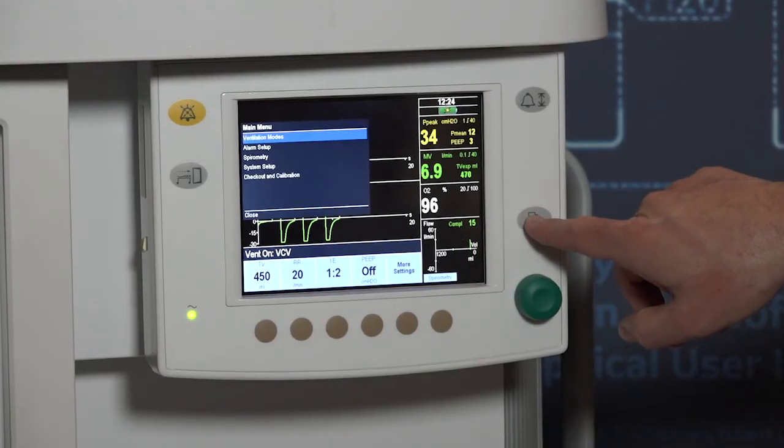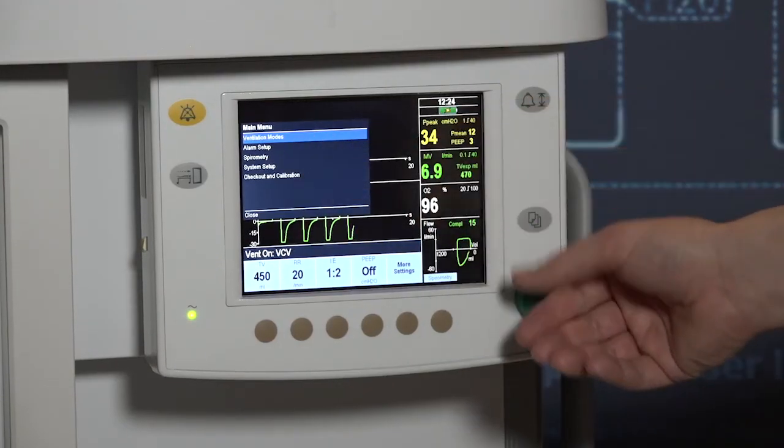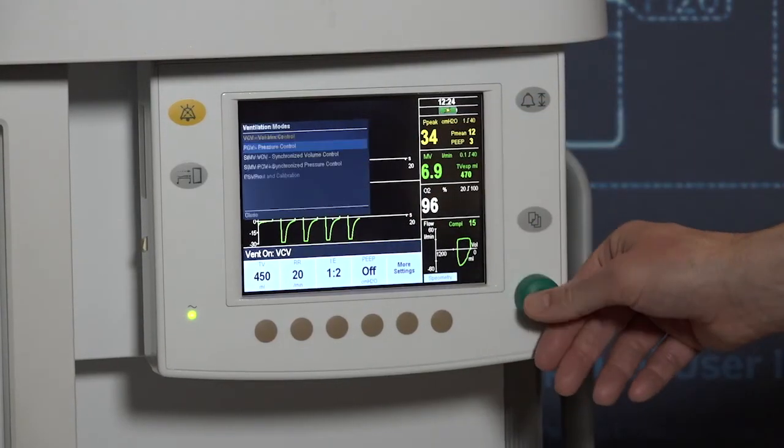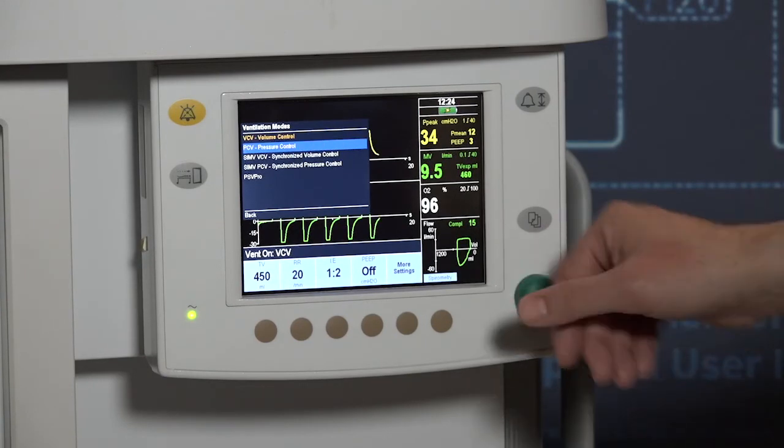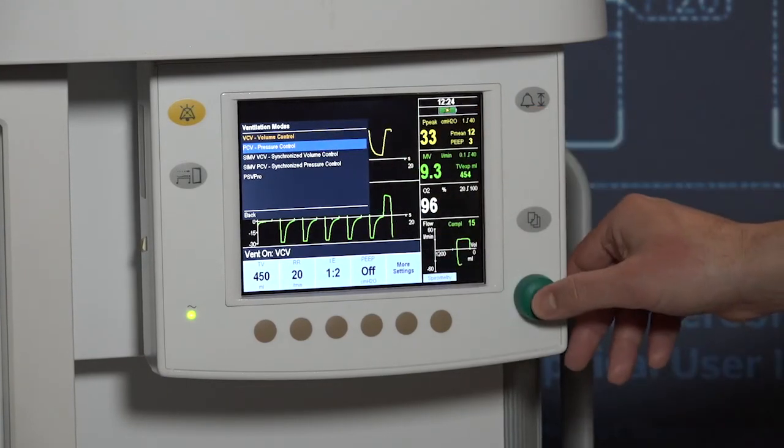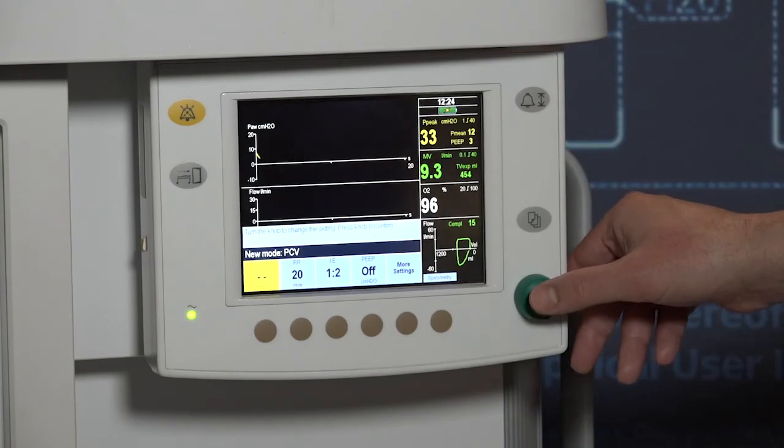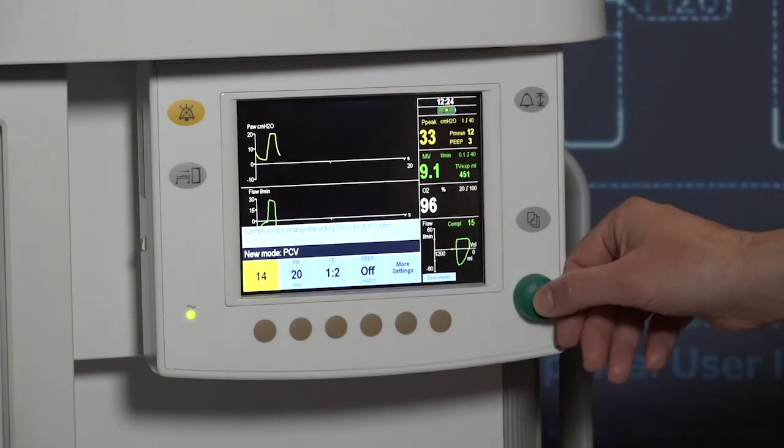To change the ventilator settings, press the hard key for the ventilation setting to be adjusted. Use the ComWheel to adjust the desired value and press the hard key or press in the ComWheel to confirm.